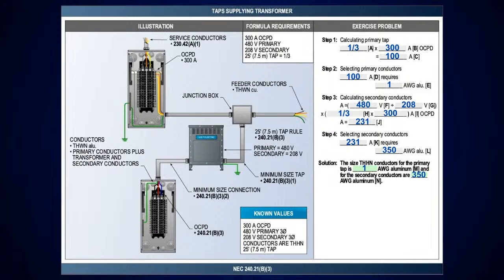Okay? Now, when I look at calculating the secondary conductors here, I need the ratio of the transformer. So I'm just going to take the 480 volts divided by the 208 volts. Then I'm going to multiply from that point a third of the 300 amp overcurrent device. That's going to give you 231 amps. The next size up above that is a 350 kcmil aluminum.